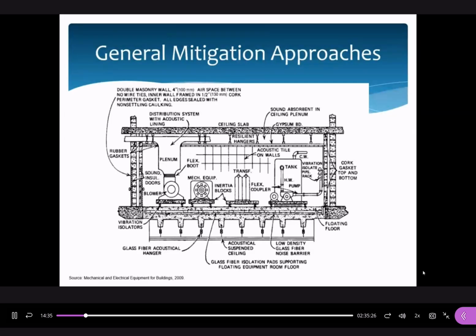For example, inertia blocks: we install inertia blocks to support mechanical equipment, and underneath this inertia block we install metal springs. I already explained that if we just install metal springs alone, we can only reduce a certain amount of vibration energy, but with the presence of inertia blocks, we can further reduce it—minimize it. It's similar to what we call the floating slab track, which also reduces vibration energy in various designs. Below the floating slab we still have to install metal springs; otherwise, without these springs it behaves like a total mass, and the force may be directly transferred from the mechanical equipment to the supporting structure. But installing metal springs allows it to perform as vibration isolation, transferring from one energy form to another. So this is a good combination of using inertia blocks together with metal springs.